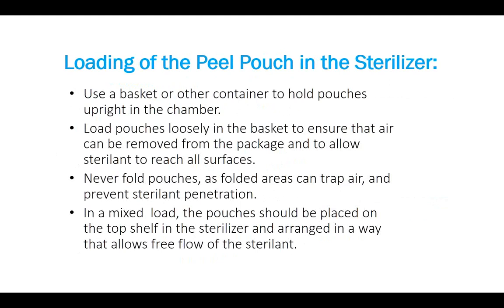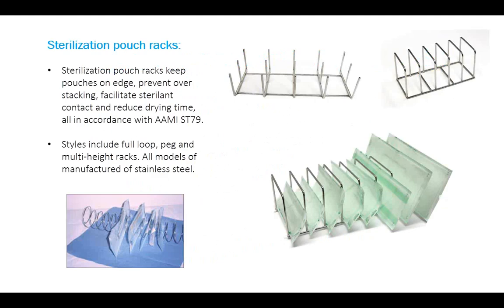Critical thinking skills, understanding the basics of peel pouching 101. In a mixed load, the pouches should be placed on the top shelf in the sterilizer and arranged in a way that allows free flow of the sterilant. You can buy sterilization racks, many different sizes and shapes. They're out there. The standard supports you for doing it. Your OEM and your sterilizer probably have information on that.